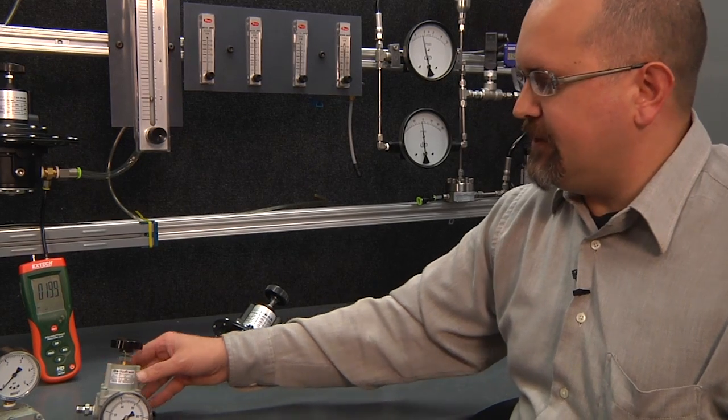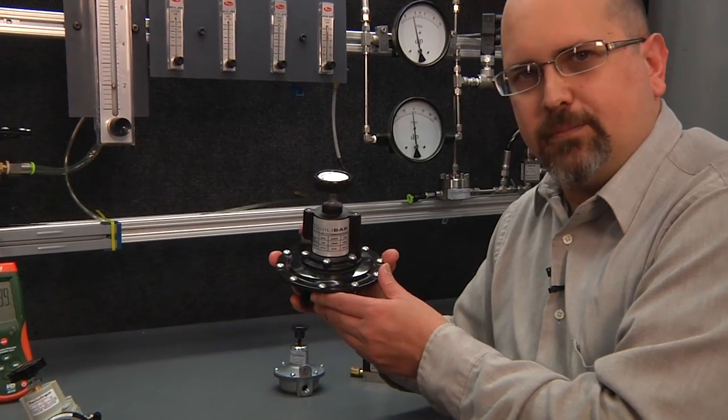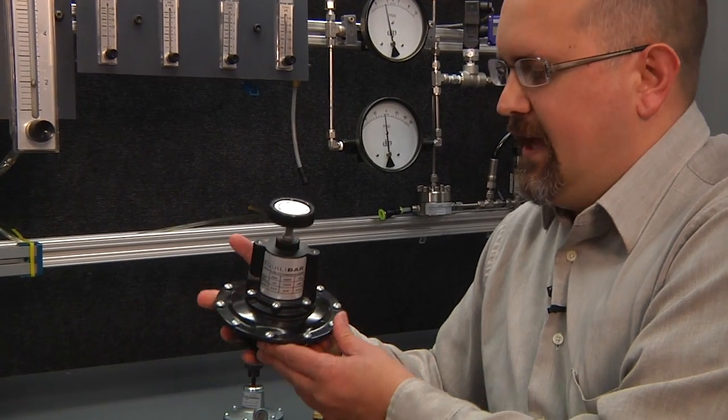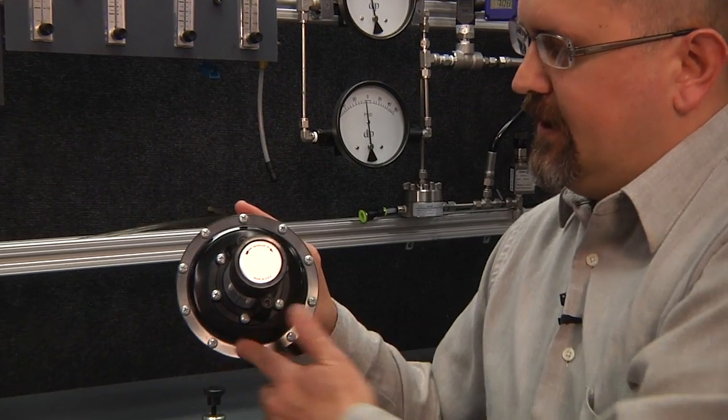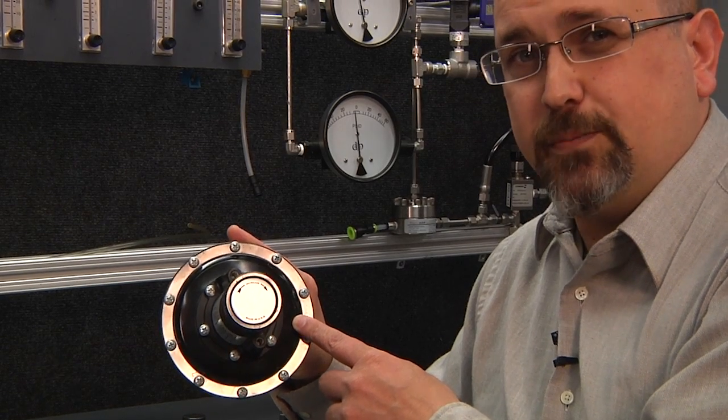What you really need to do is increase that diaphragm surface area as we've done with this Equilibar pressure reducing model. You can see in this model it has a much larger diaphragm sensing area that is able to detect those very low pressures.